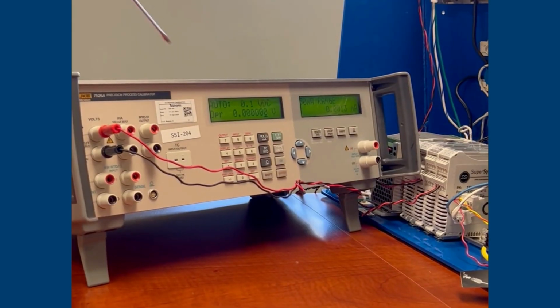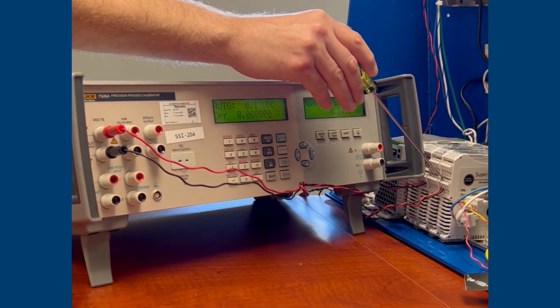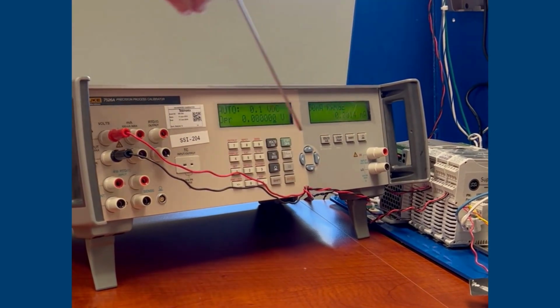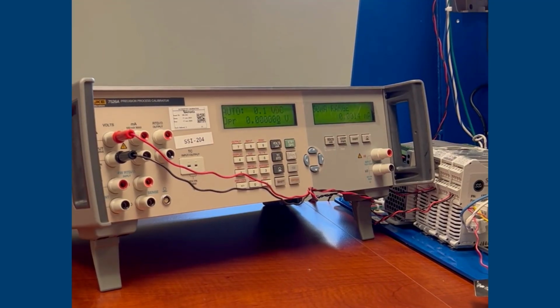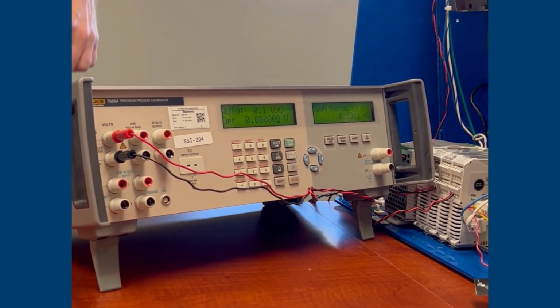From here, we are going to select which input we are going to calibrate. We can do these one at a time, or if we have multiple plugs and wires, we can do multiple at a time. We are choosing input 1, and we're going to calibrate for 0. This is currently displaying what it's measuring on the input. So we're going to source to it 0 volts. This would be sourcing through copper wire to the analog input 1 of module 1, 0 volts DC.